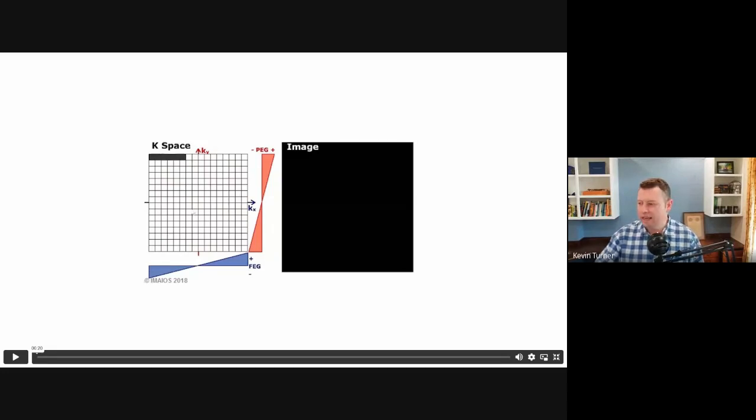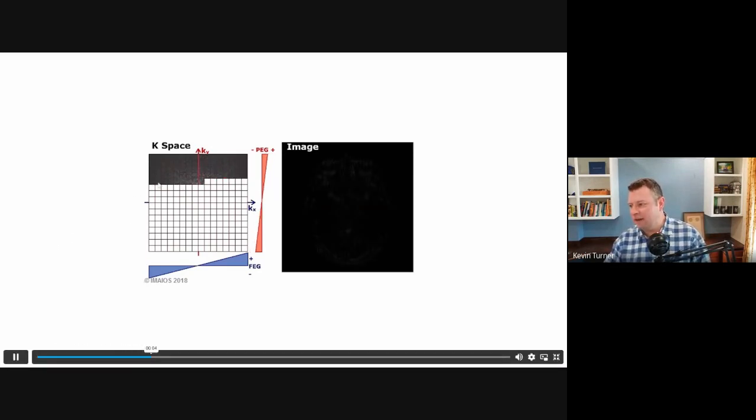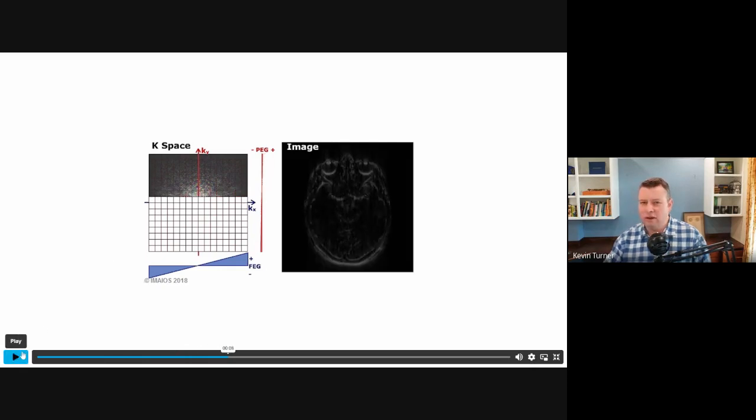We're looking at just K-space and then the image, right? The patient is not shown here. So as we fill up K-space, we start to create the image. So we fill up one line of K-space, then the next line of K-space. Every one of these lines of K-space is a different echo. There's an echo, there's an echo, there's an echo, right? And each one of these echoes had a 90-degree excitation pulse, a 180. We collected the echo. We waited till time TR and did another 90-degree, and so on and so forth.